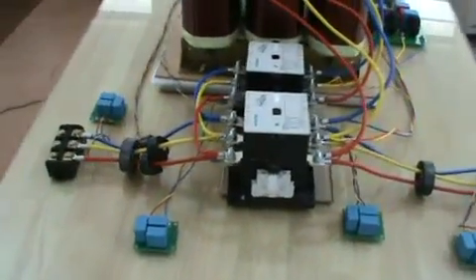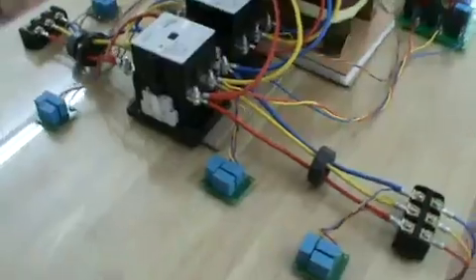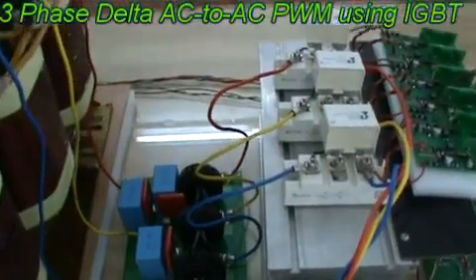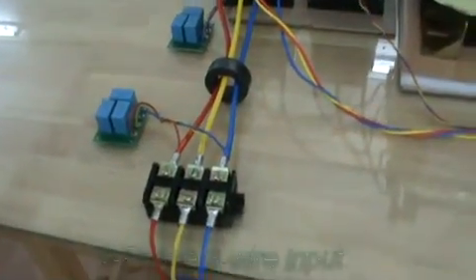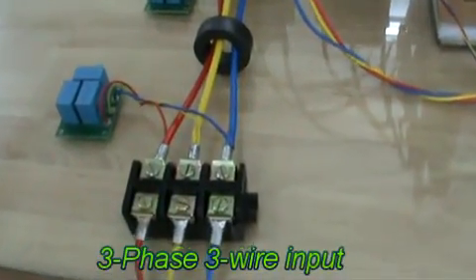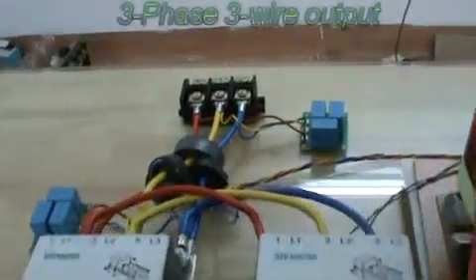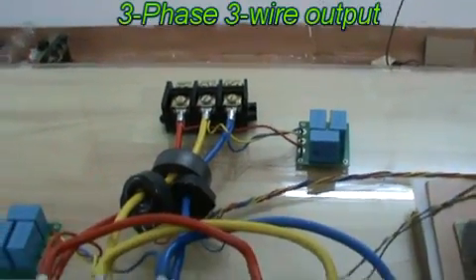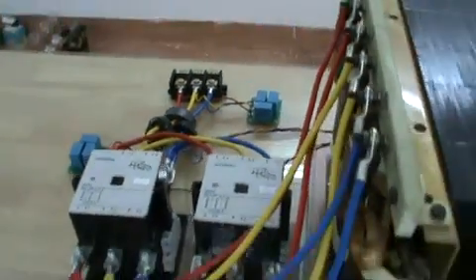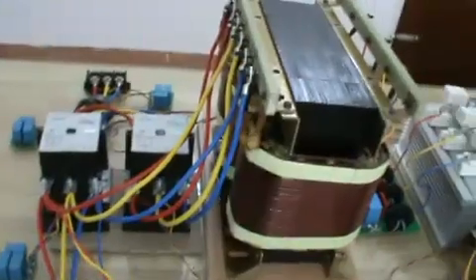Voltage optimizer or stabilizer is for energy saving or regulating the voltage. Our system is based on direct AC to AC PWM using IGBTs. The main advantage of this system is it works without neutral. Only 3-phase 3-wire input is required. The 3-phase 3-wire output has a potential with the existing neutral, so single-phase load can be connected from any of the phase output to an external neutral.